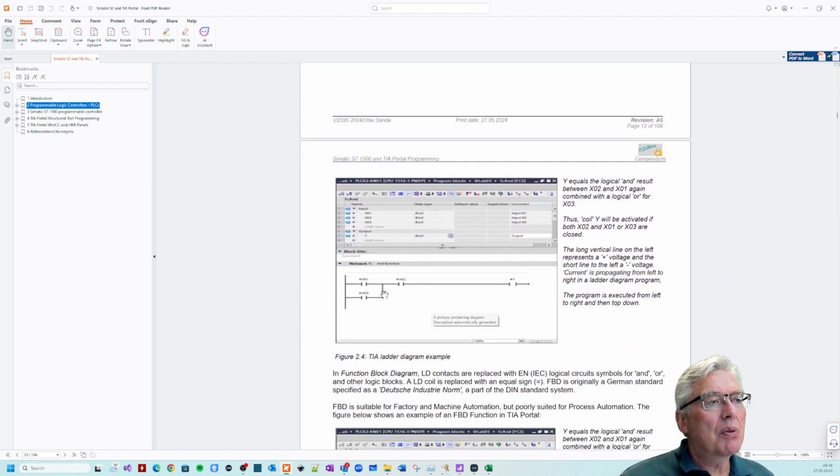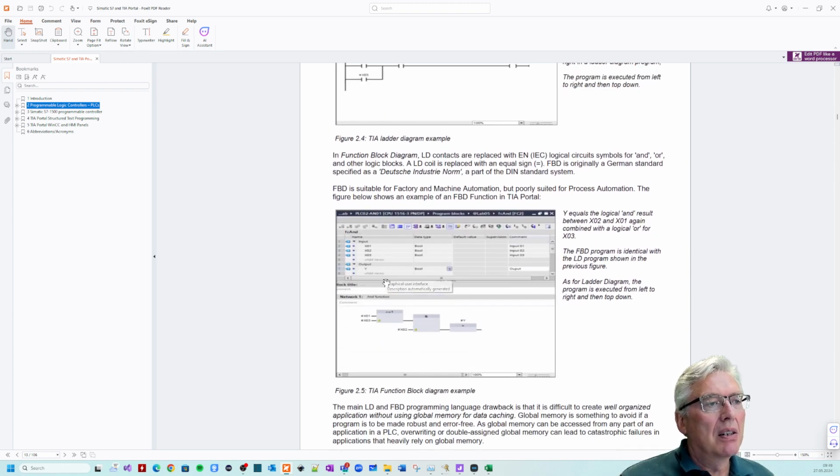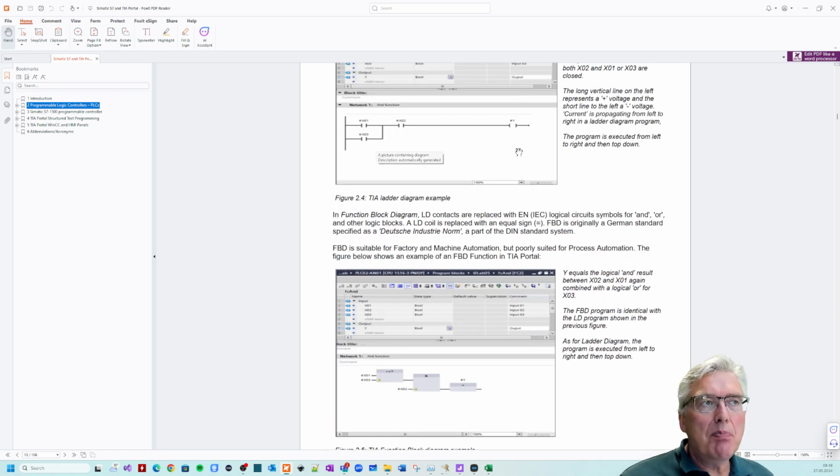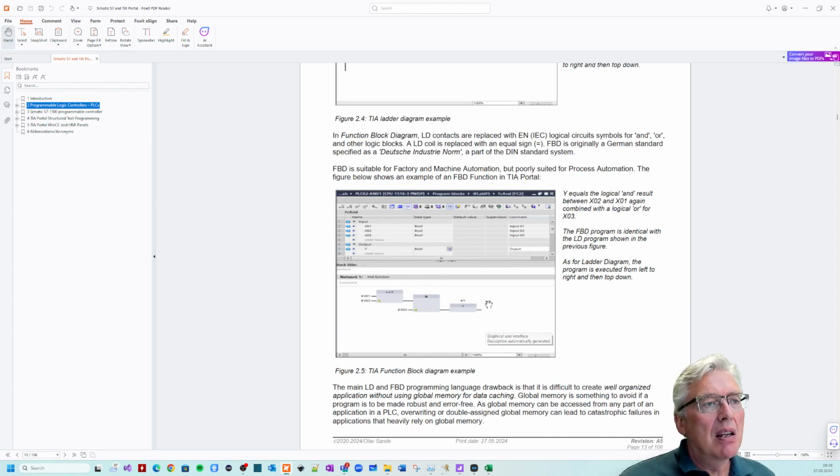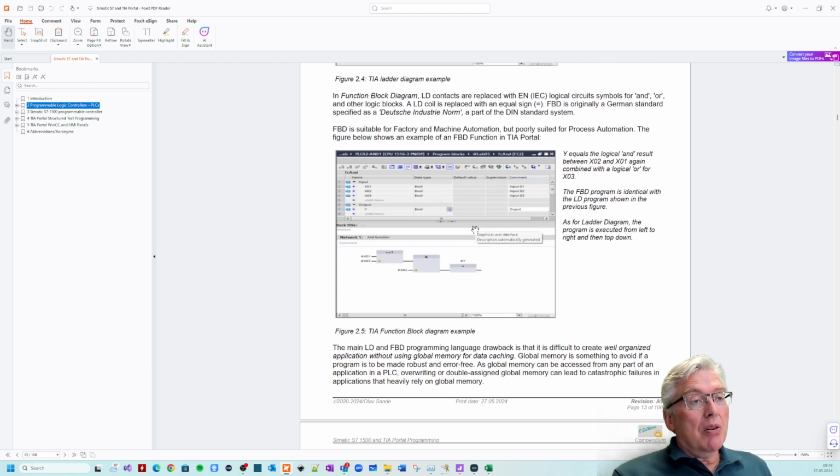So here's ladder, it's energy flow. These two contacts are closed, then you get energy to your coil and a motor starts or whatever. And here's an OR, so there's an OR and an AND, which would look like this in FBD. Ladder is better than FBD because in FBD you have to decode your logic. Here you can look at power flow, which is more intuitive. But in FBD, this is the German standard, you have to decode the logic. And if it gets complicated, of course, there are errors everywhere. And if you bring in memory elements, good luck. So sequential logic, combinatory logic, and memory elements.